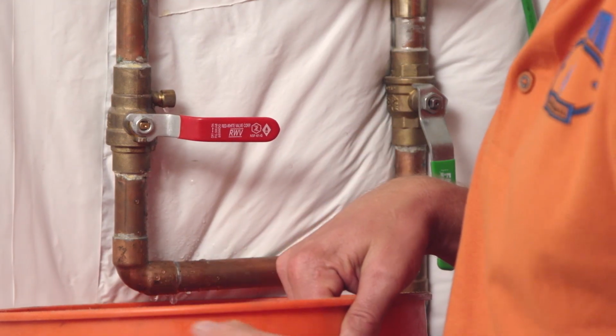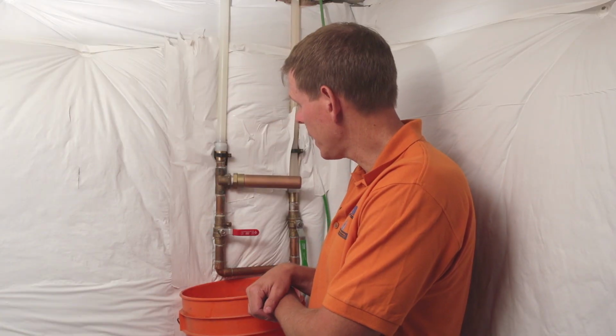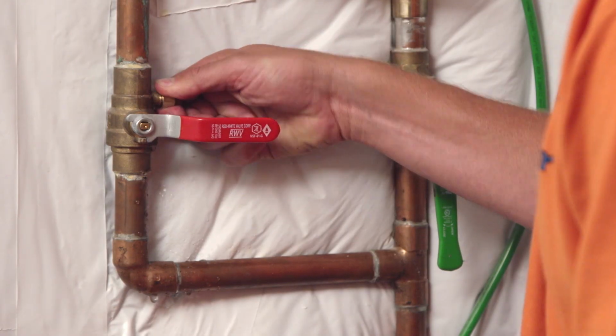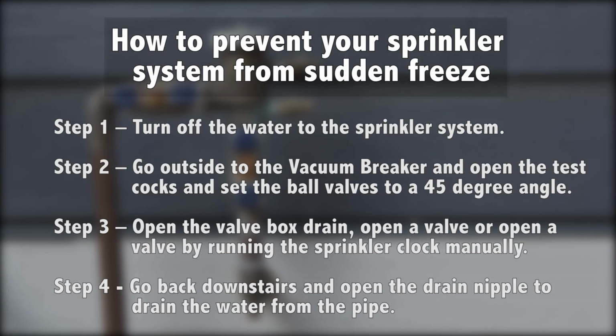If it's a really long pipe, that might take a few minutes. If it's a short pipe like this one, it goes pretty quick. Now that the drain nipple is done draining, all I need to do is tighten the drain nipple, and that's the end of draining the basement pipe. If you follow the steps that we've listed out in this video, you should be able to protect your backflow preventer and the pipes that are outside in case of a sudden freeze.